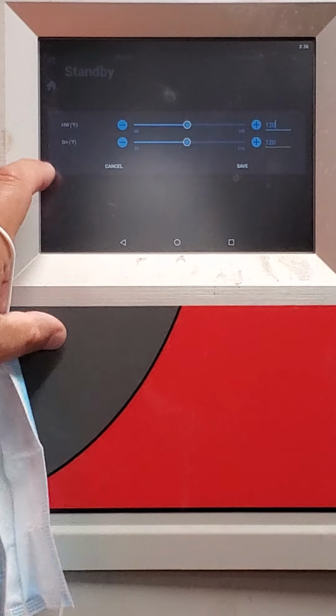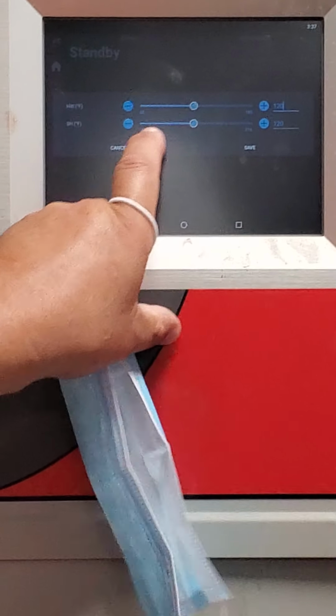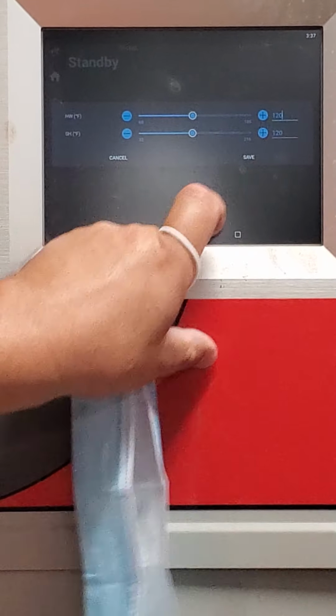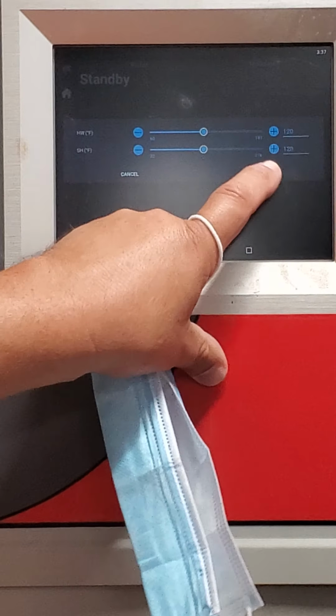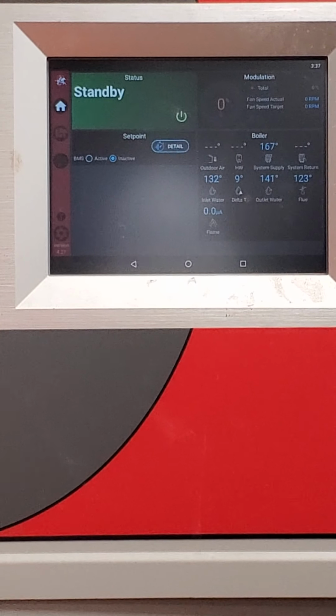These boilers have a set point button. It's under detail, and you would be looking at the space heating set point. If you make a change, just press save, or cancel if you don't want to make a change.